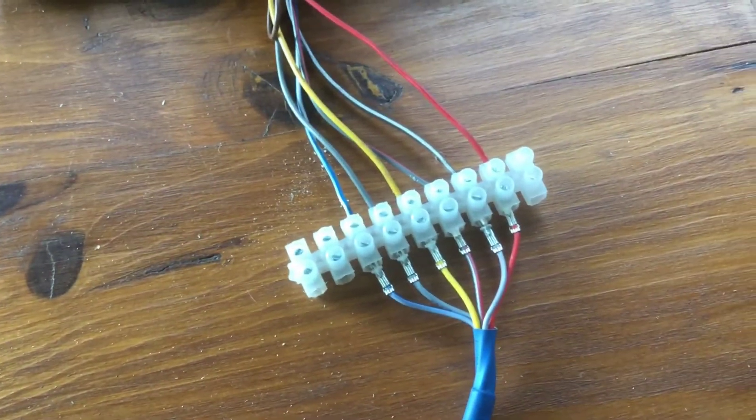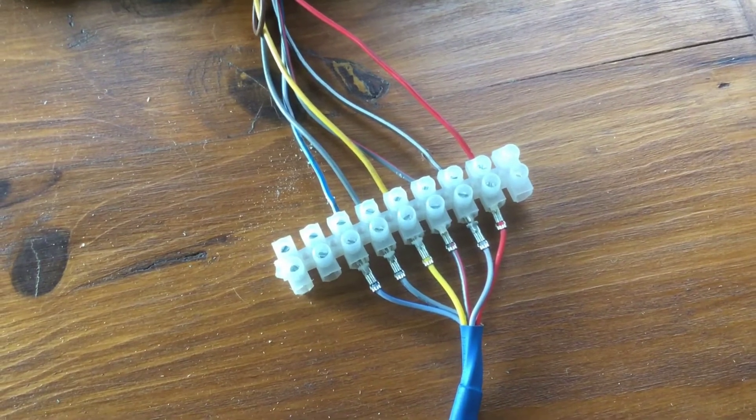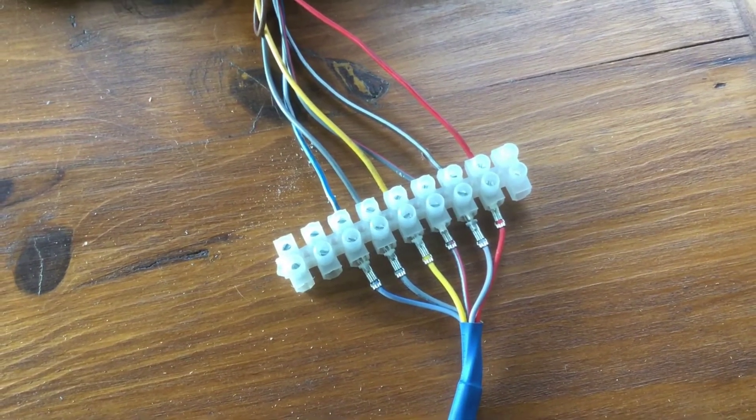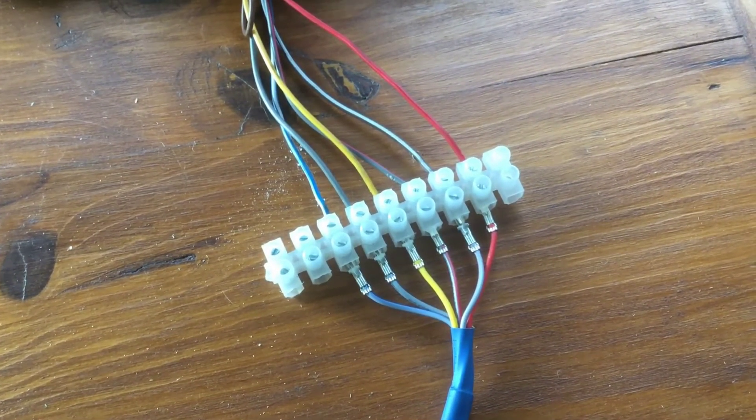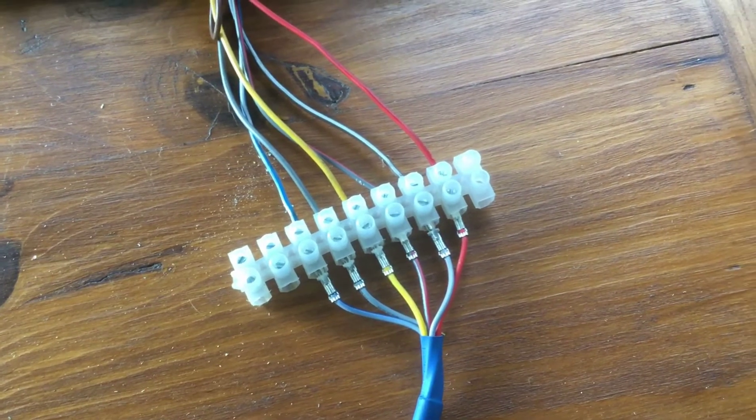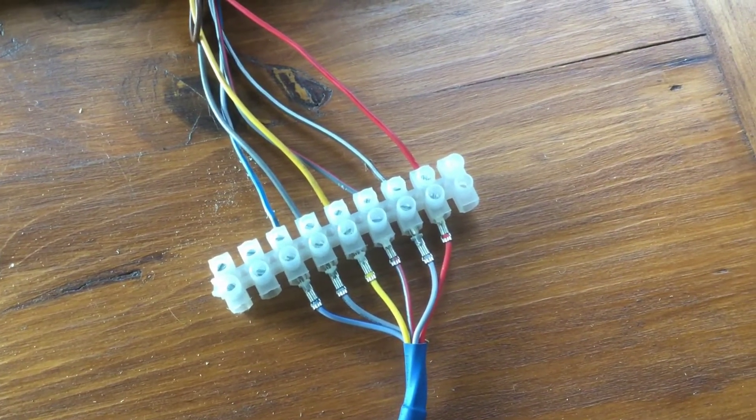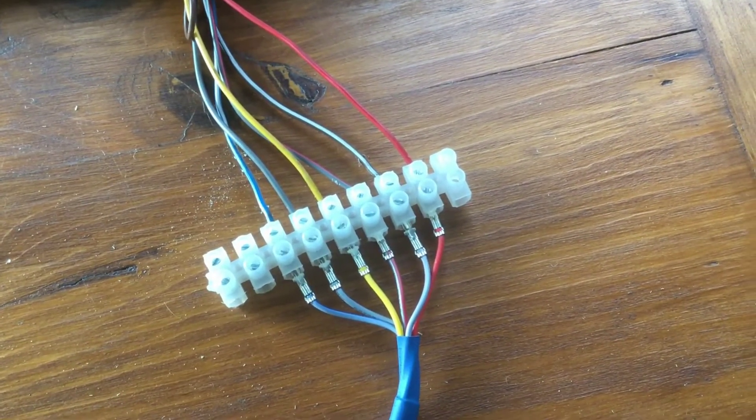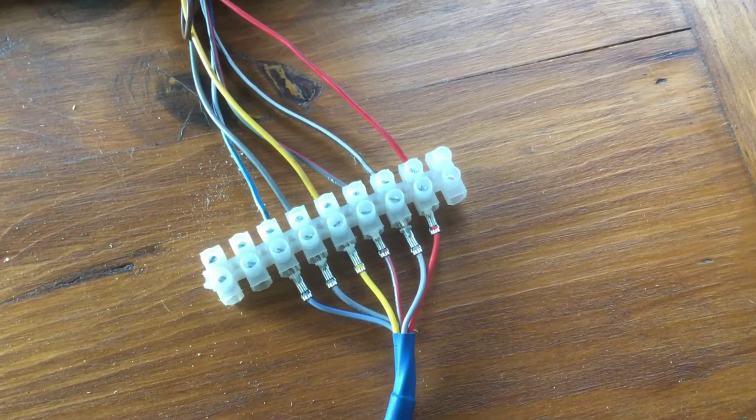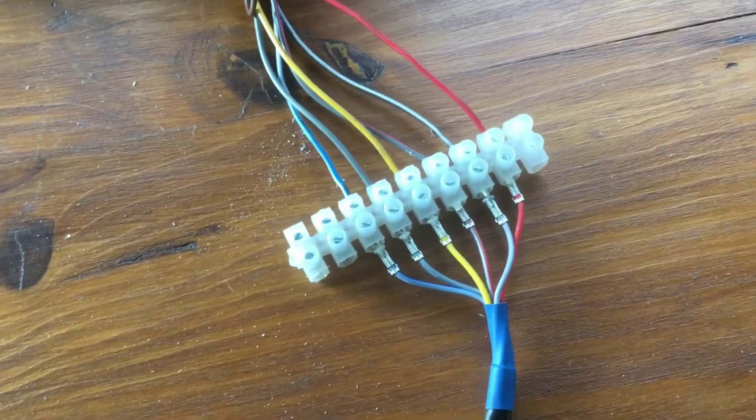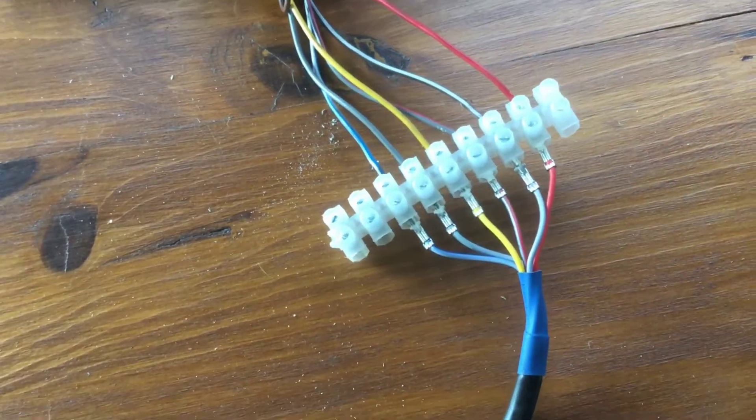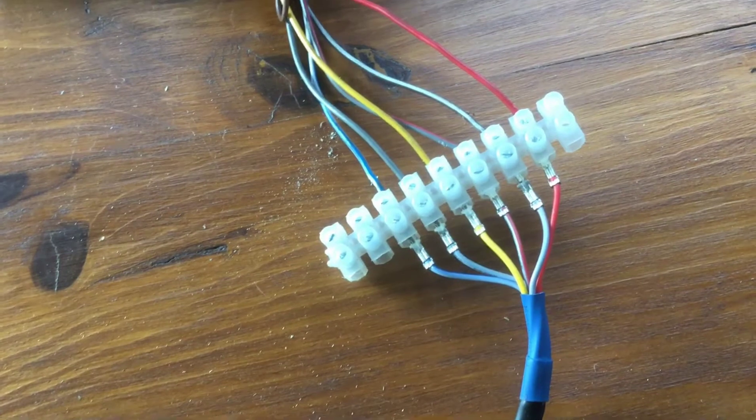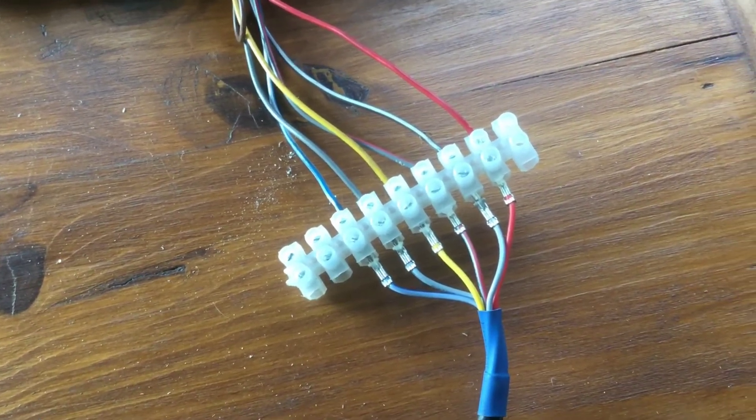Then we have the yellow wire. That is the on-off power to the heater from the controller. That is actually what turns the heater on. Then we have a grey and red one. That is the primary temperature sensor. That is the one that the controller actually uses to turn the heater on and off based on the required temperature.